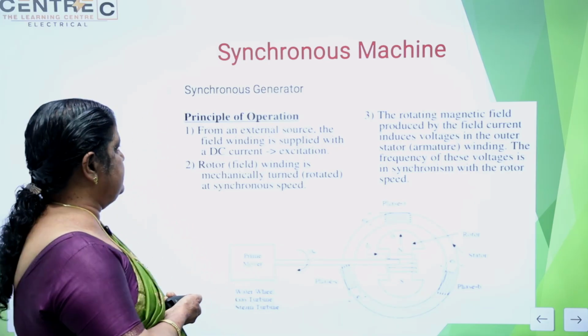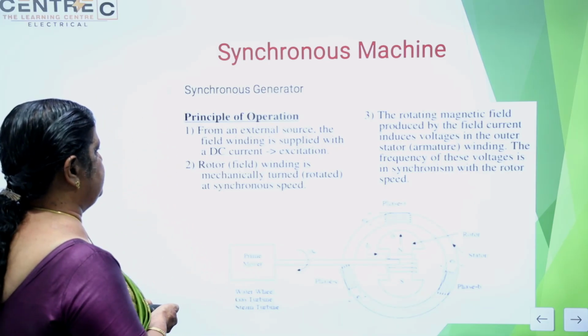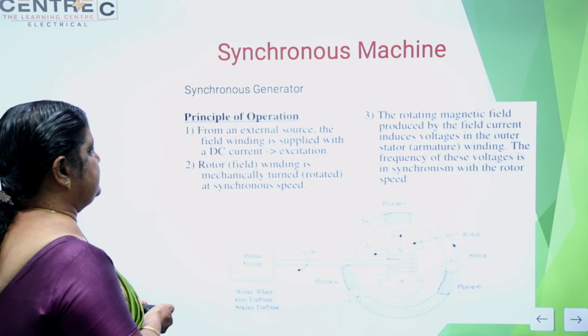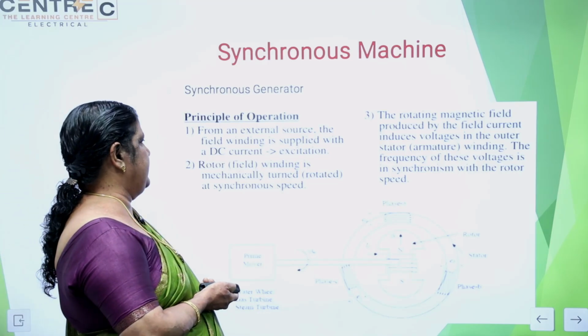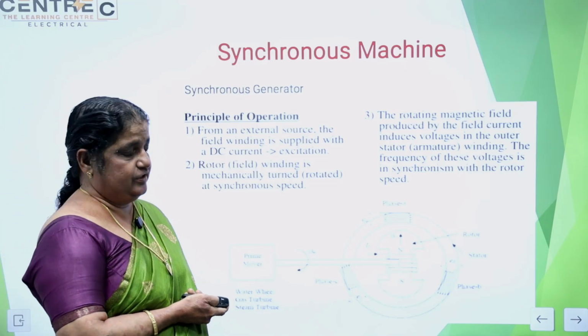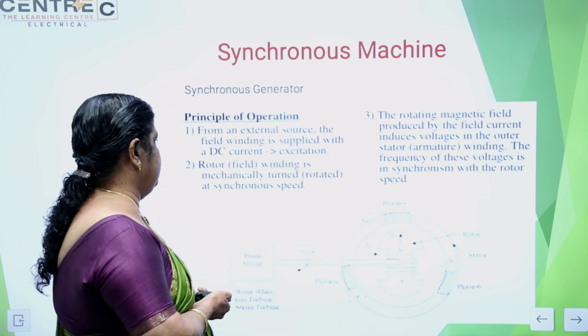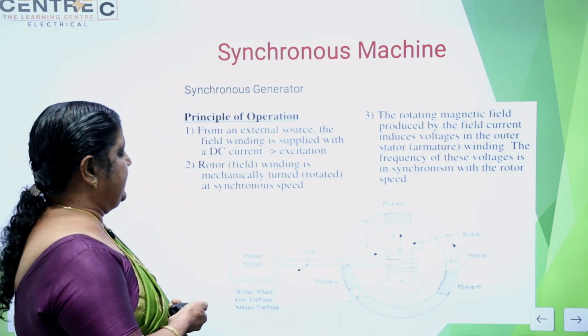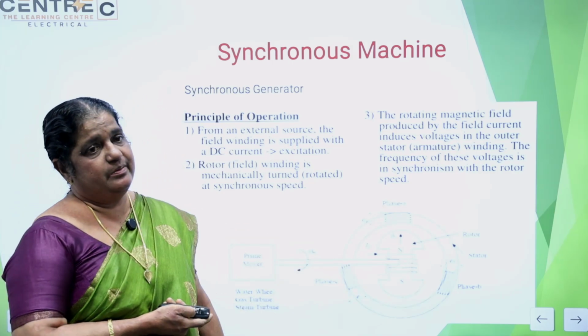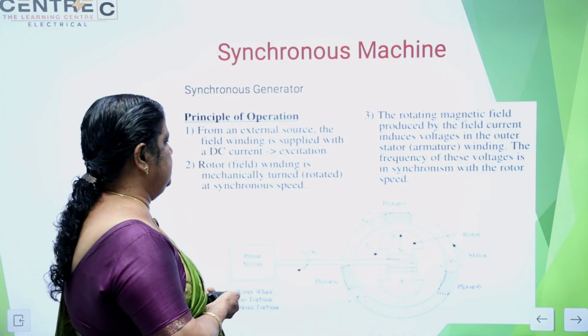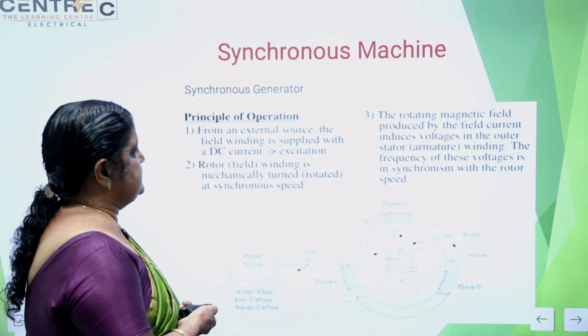Then this is the principle of operation of a synchronous machine. From an external source, the field winding is supplied with a DC current. So the winding is excited. Then the field winding is mechanically turned. Along with that, we mechanically rotate it. When it rotates, it rotates at synchronous speed.